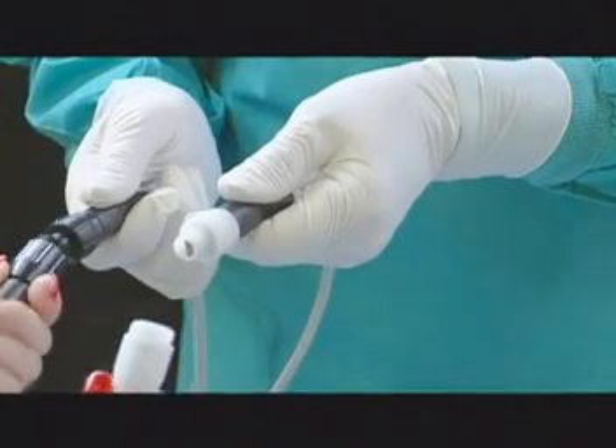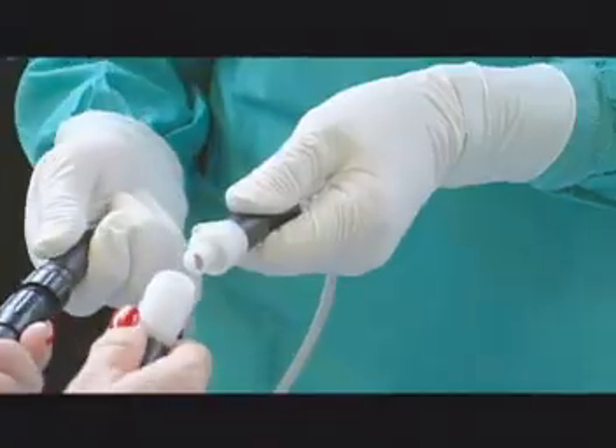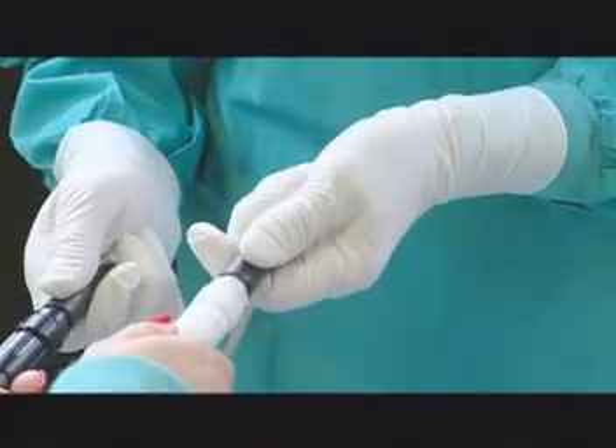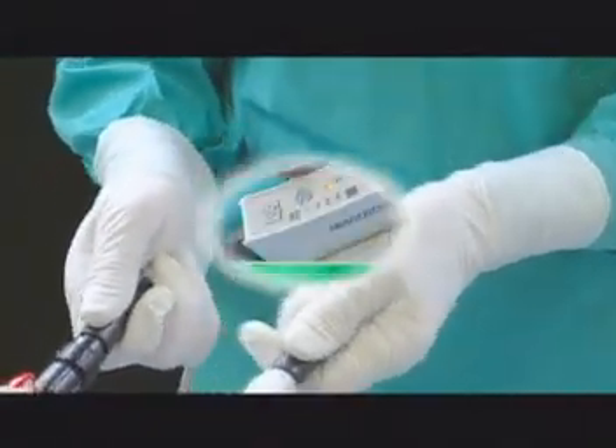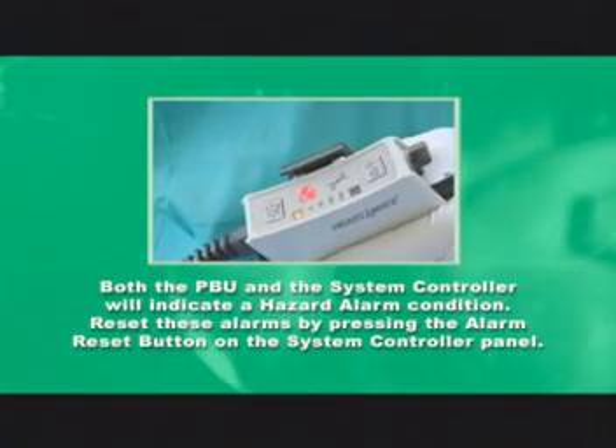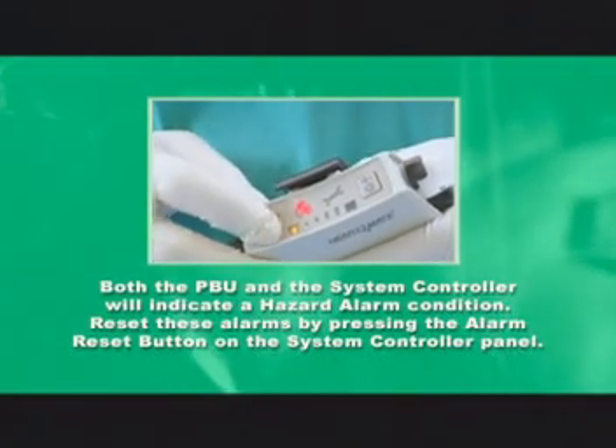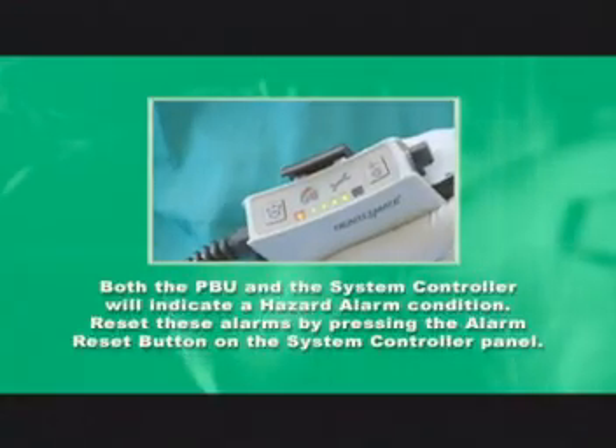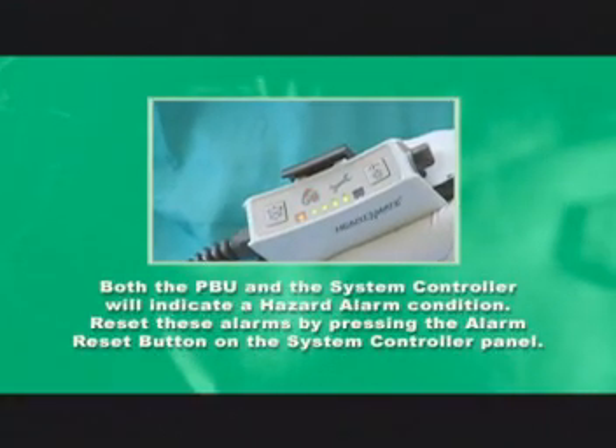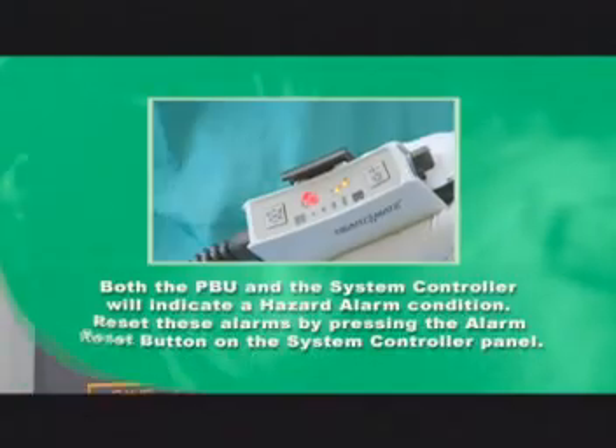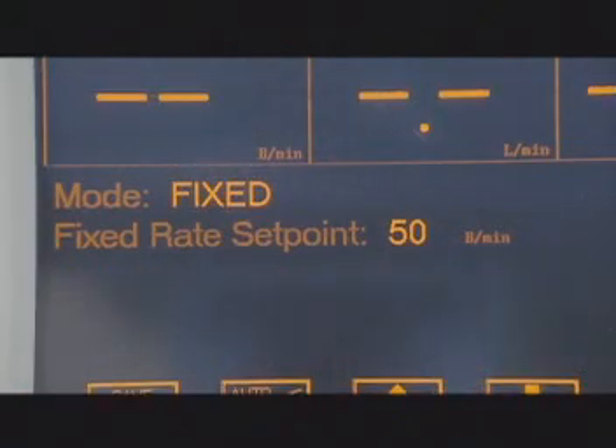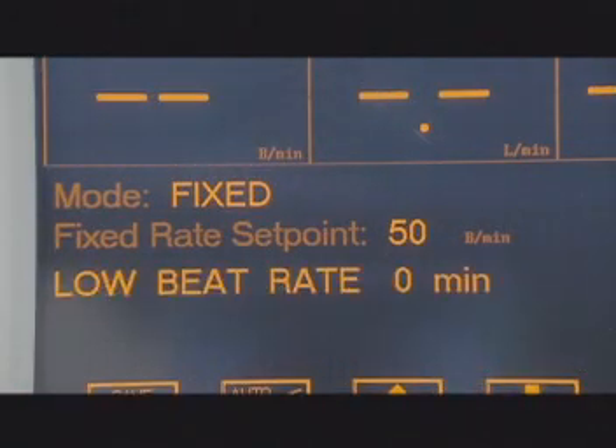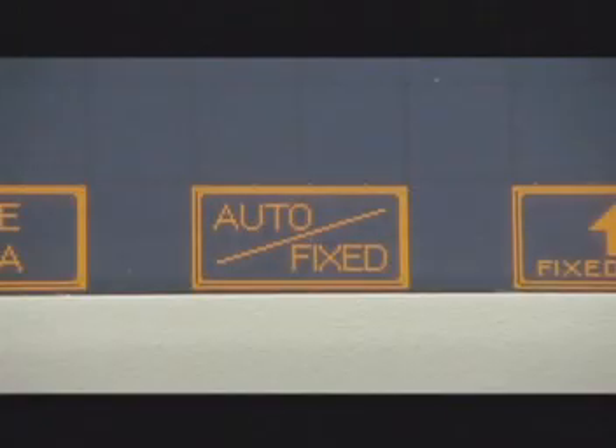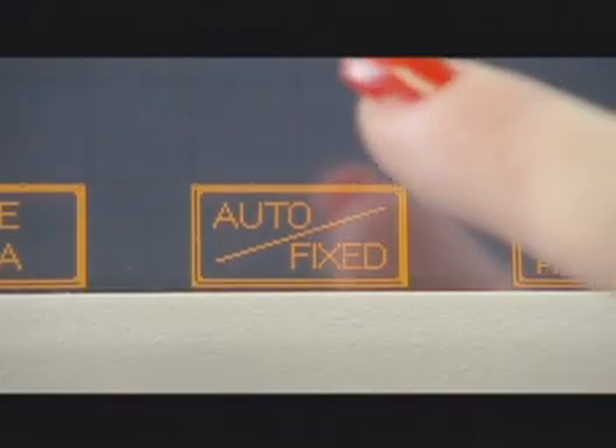Pass the two sterile system controller power leads out of the sterile field and connect them to the bifurcated ends of the PBU cable. Note, both the PBU and system controller will indicate a hazard alarm condition. Reset these alarms by pressing the alarm reset button on the system controller panel. Examine the system monitor to ensure that the controller is in fixed rate mode and set to operate at 50 beats per minute.